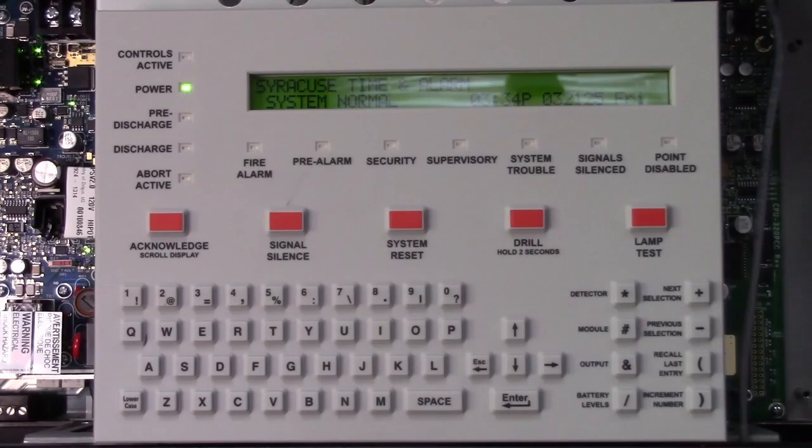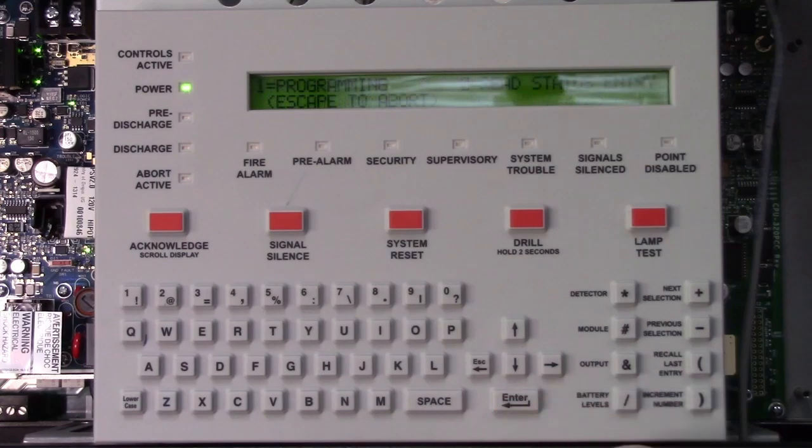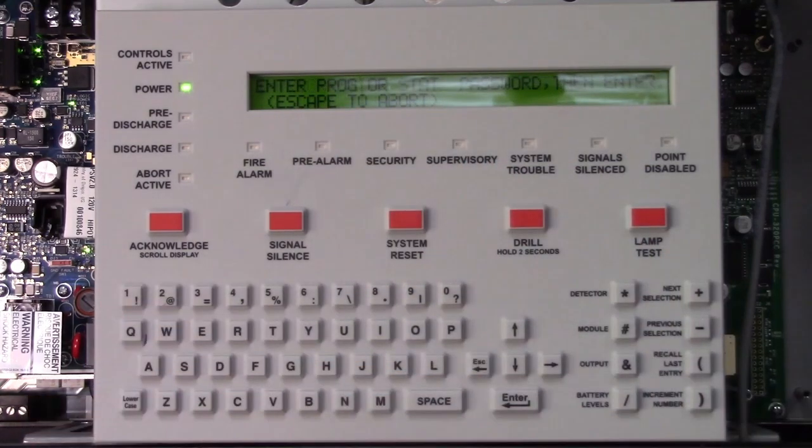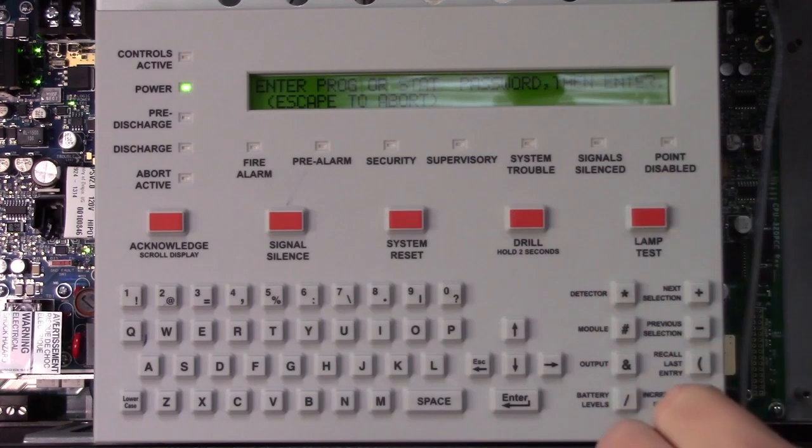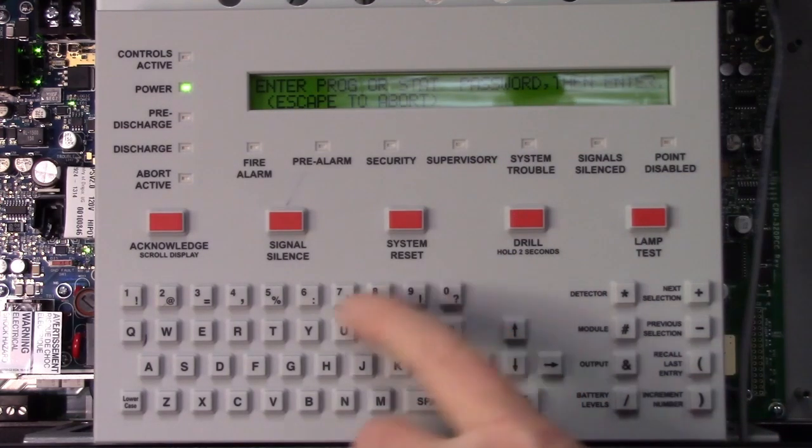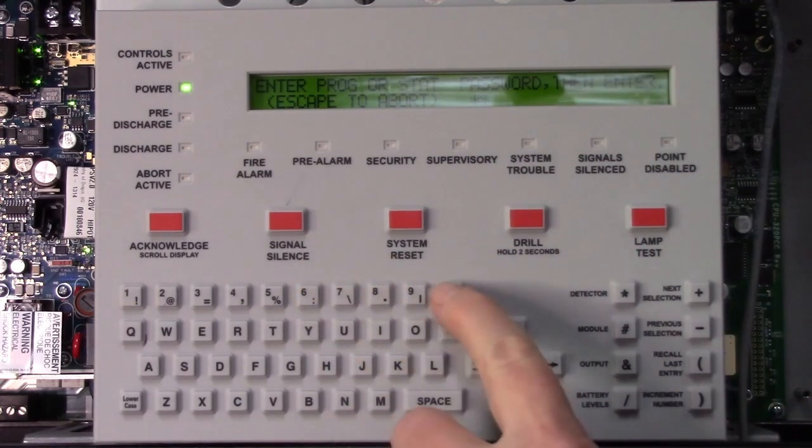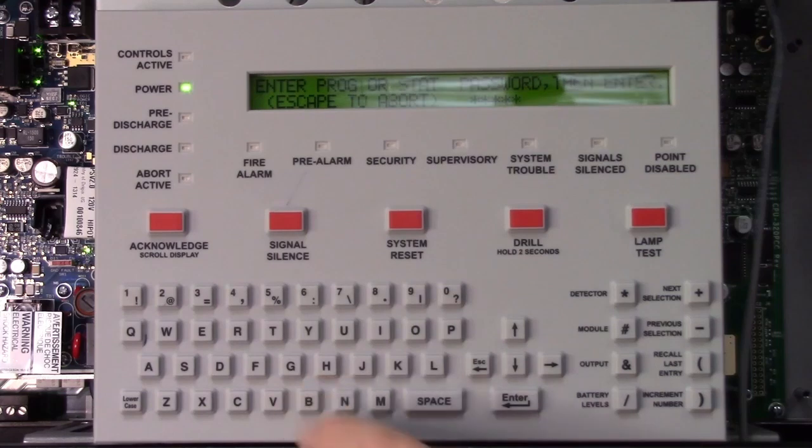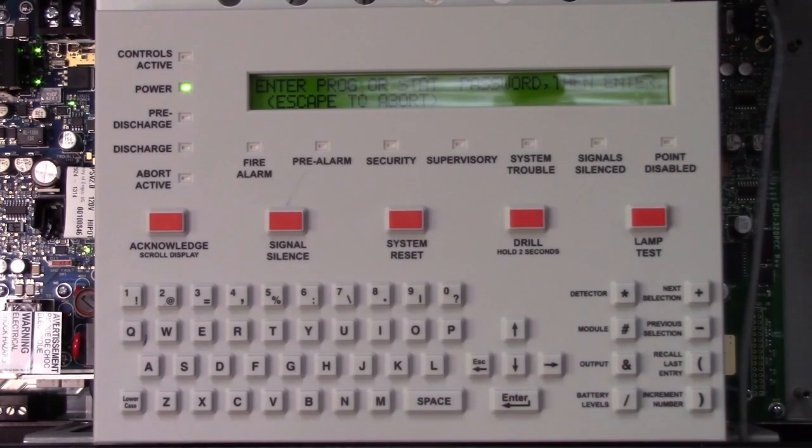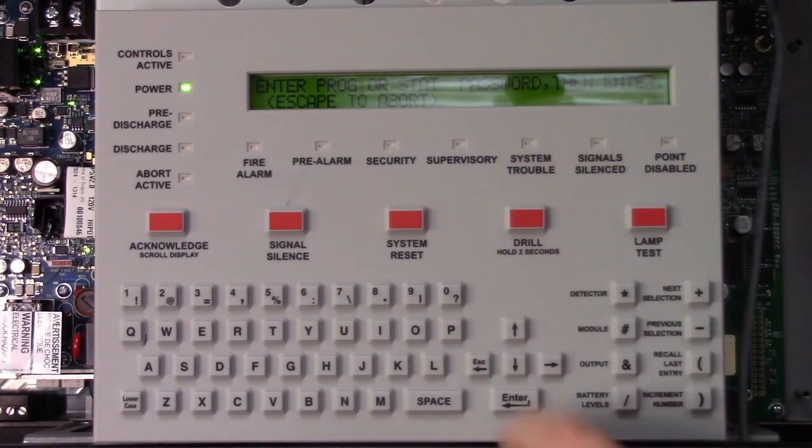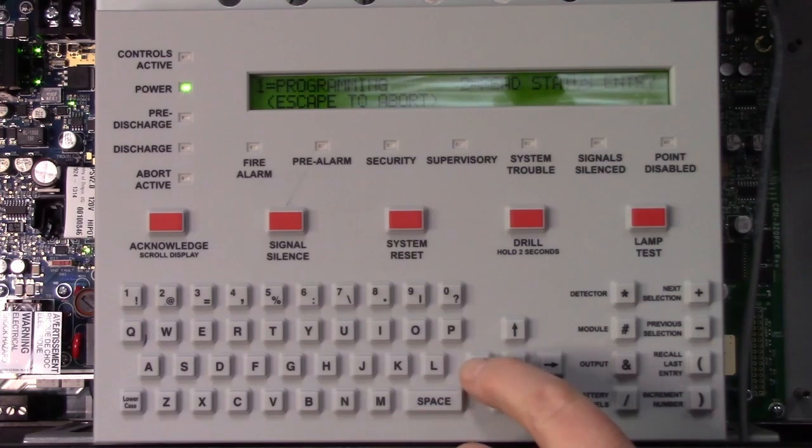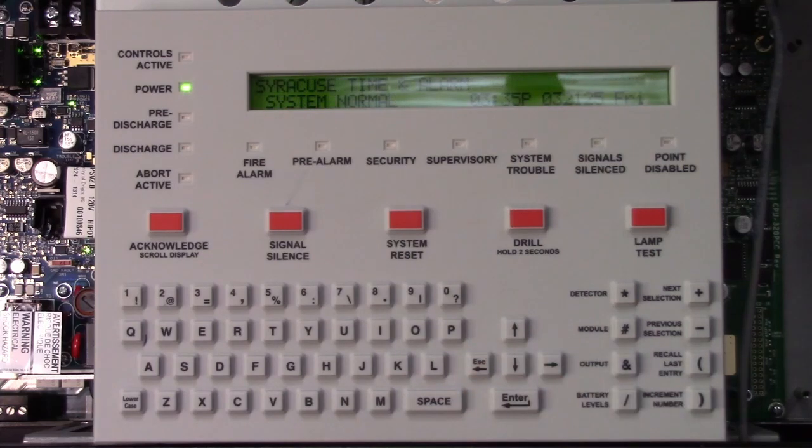To set the baud rate to 9600 for the printer port, start by pressing enter. Press 1 and go into programming mode, and the password you're going to enter is 9600B. Press enter, and now you've set the baud rate. Just escape back out, and you should be good to go.